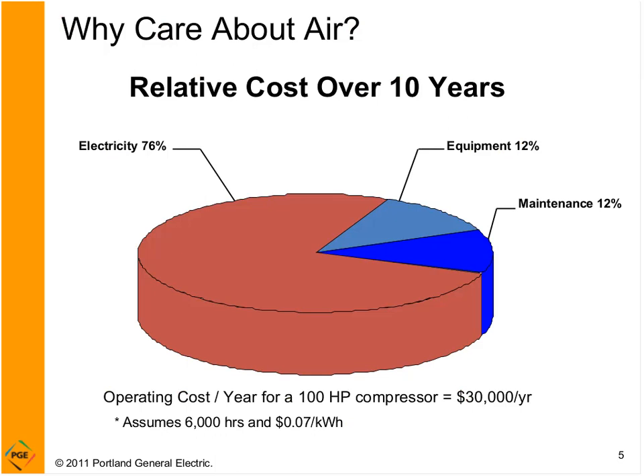If we look at the life cycle of a compressed air system over ten years, approximately 12% of that cost goes to purchasing equipment, and maintenance is another 12%. The most important piece: 76% of compressed air expenditures go to electricity. So whether you nickel-and-dime your equipment, what really makes a big impact is electricity use. Keep that in mind when purchasing equipment — it may be worth buying the energy efficiency option.